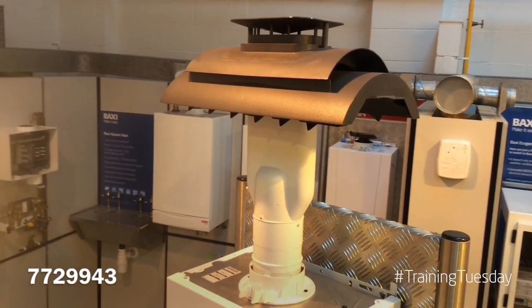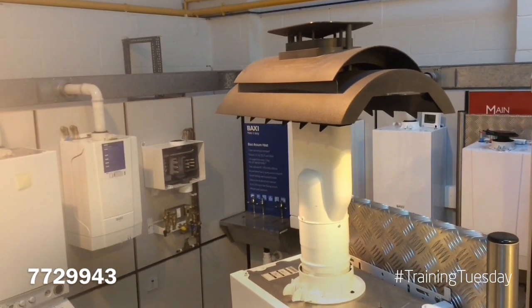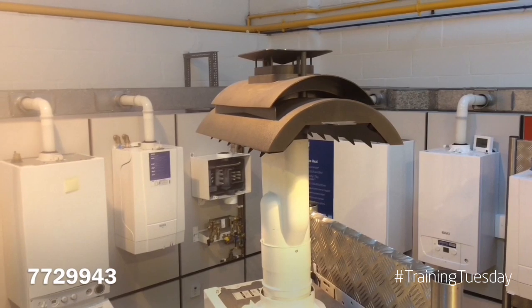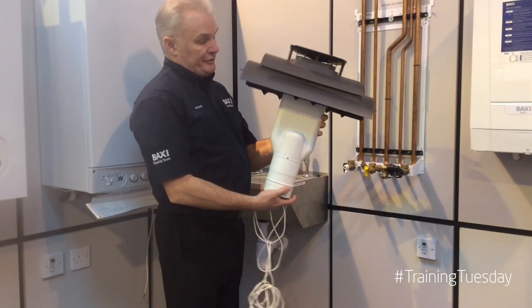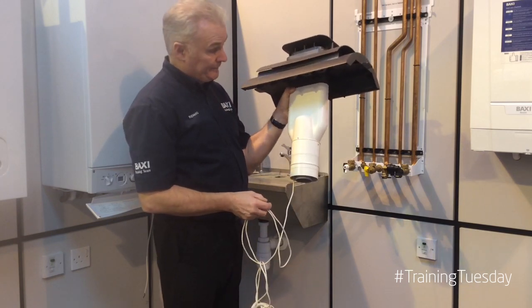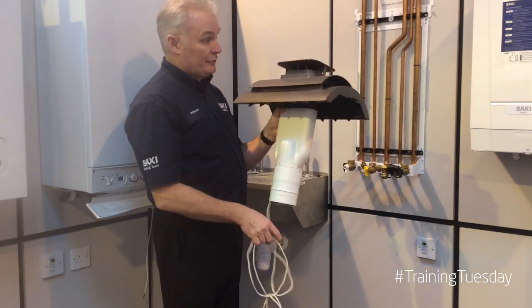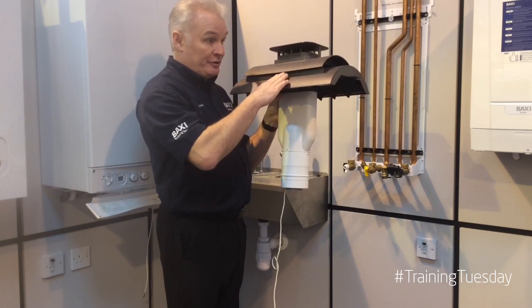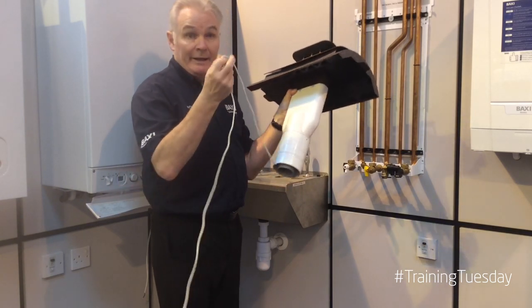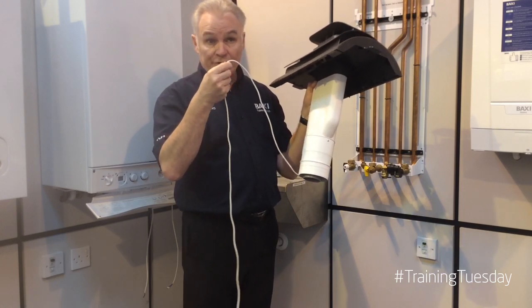Finally, the last accessory we're going to take a look at is the Baxi Multifit Flue Ridge Tile Termination Kit, part number 7729943. This is the vertical ridge tile termination kit. It goes onto a four-inch Multifit Flue system and sits onto the top. You've got your air intake coming in below the shroud on the sides, and your exhaust terminated from the top. Incorporated in the kit is the IFOS — Inflow Outside Sensor — so you can utilise weather compensation if you so choose.